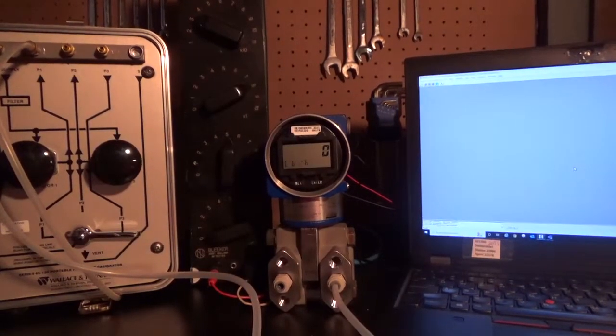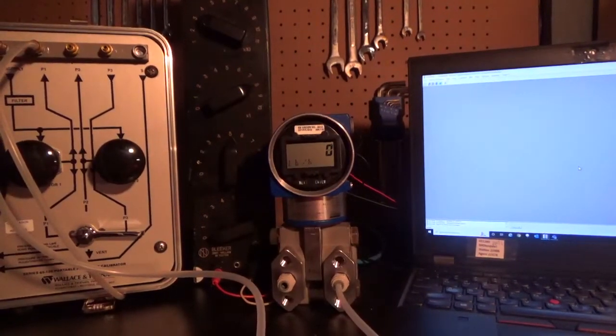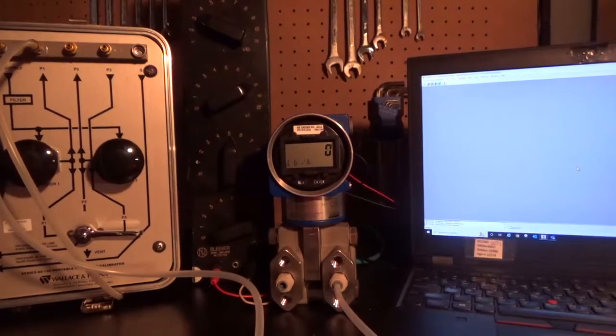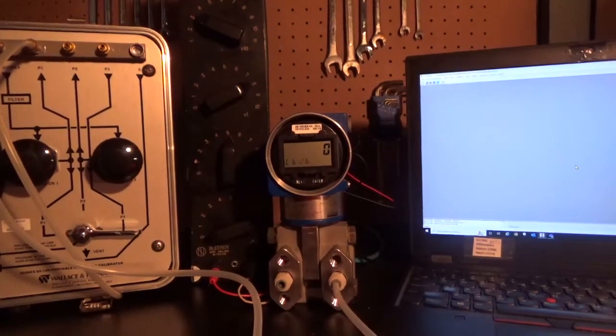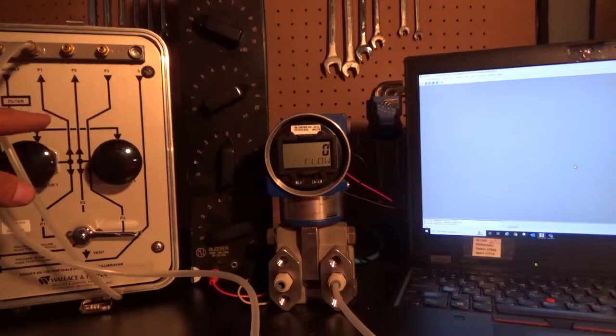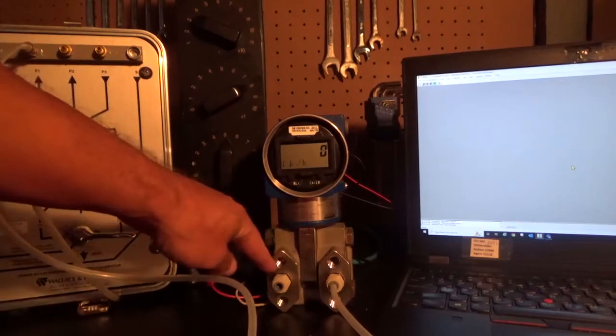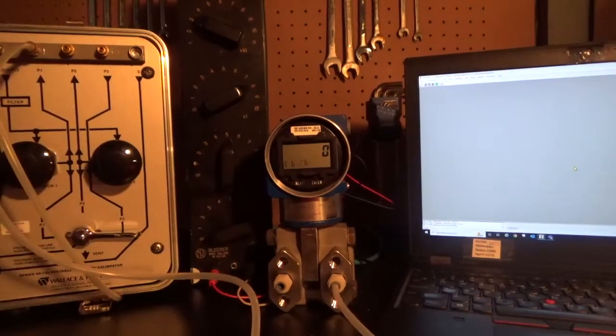When performing a two-point differential pressure calibration, you need only connect your pressure source here to the high side of the IMV30 transmitter with the low side vented to atmosphere.